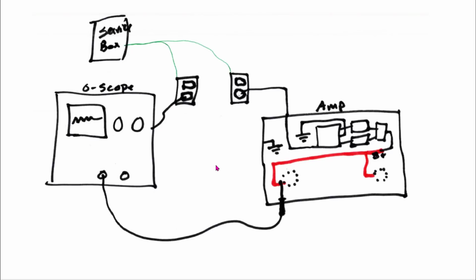And you can easily test this. All you've got to do is get out a digital multimeter. Is the amplifier ground, in other words your signal ground in your amplifier, and your chassis ground the same? So get a digital multimeter out, put it on continuity test, find the ground of the signal, and test that against the ground of the chassis. If so, you're probably fine testing your piece of gear on the bench this way.